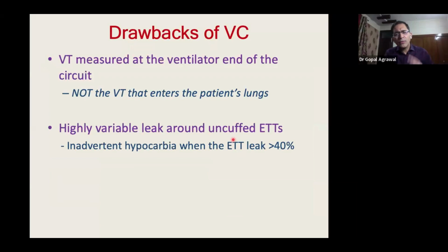So drawbacks of volume controlled ventilation: the tidal volume is measured at the ventilator end of the circuit, and there are huge ET tube leaks. So if the leak is high, volume ventilation cannot be done. I'm talking of volume controlled ventilation. There's something called volume guarantee, which we'll discuss later on. In volume controlled ventilation, tidal volume is measured at the ventilator end of the circuit, not at the patient end.